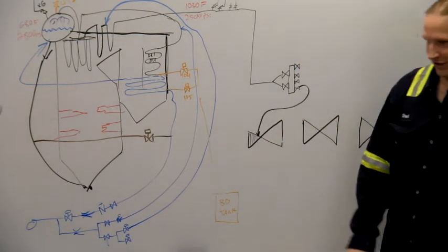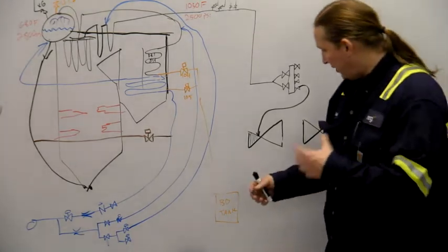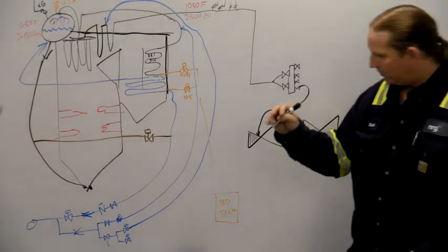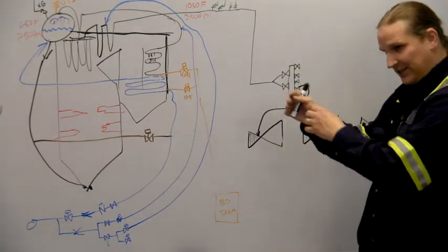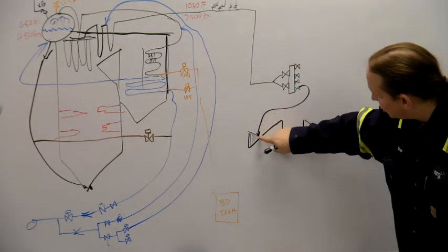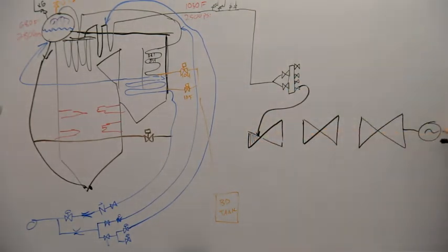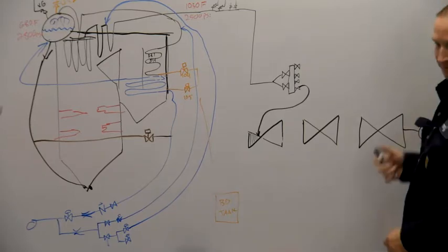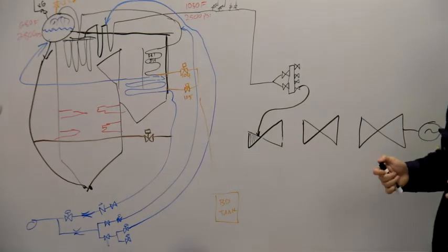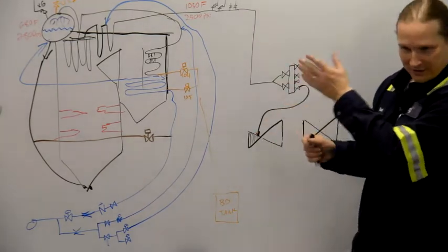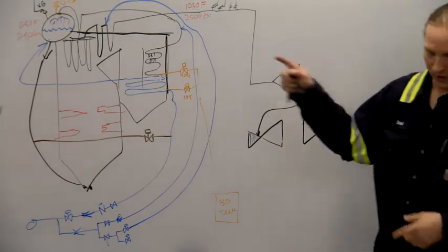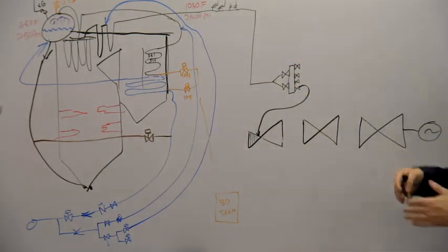Seven stages. Each stage has a fixed set of blades and a rotating set of blades. The rotating blades catch the steam as it's expanding and pushing, transferring that energy to the shaft and ultimately to the magnet at the end that's making electricity. The fixed blades redirect it so they aim it to hit the next set of blades right, instead of just getting the swirl going. They kind of curve counter to each other.